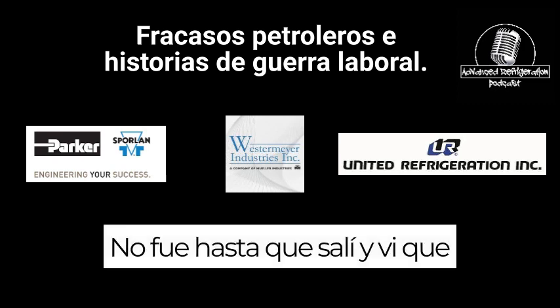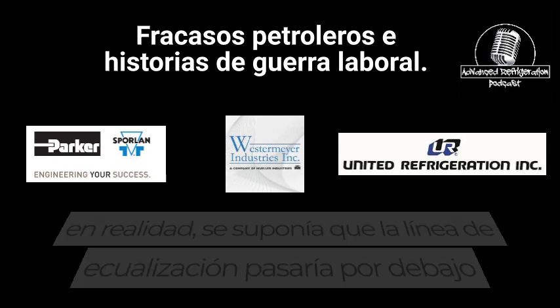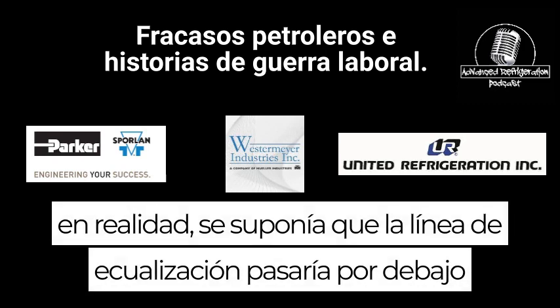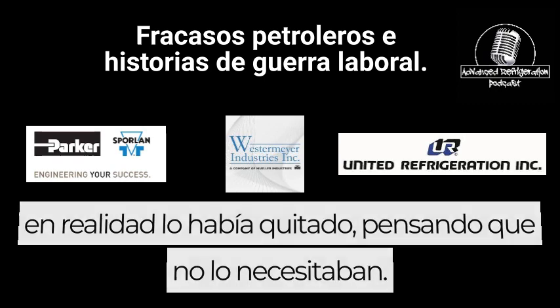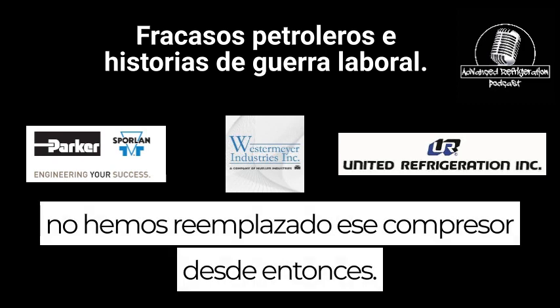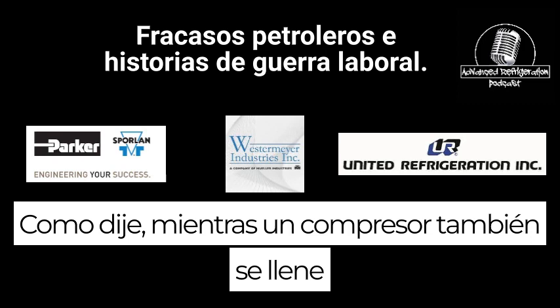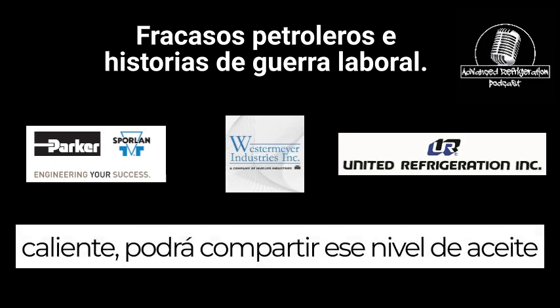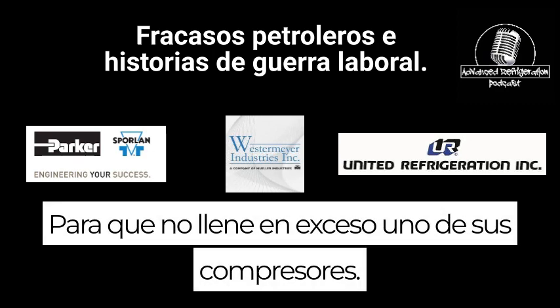It wasn't until I went out there and saw that the equalization line, which was supposed to go under the belly of this compressor, had been removed by someone thinking they didn't need it. We ended up replacing it, and we haven't replaced that compressor since. So now you guys know what the reason is for it. Like I said, if one compressor fills up too high, it'll be able to share that spare oil with the rest of the compressors, so you don't overfill one of your compressors.